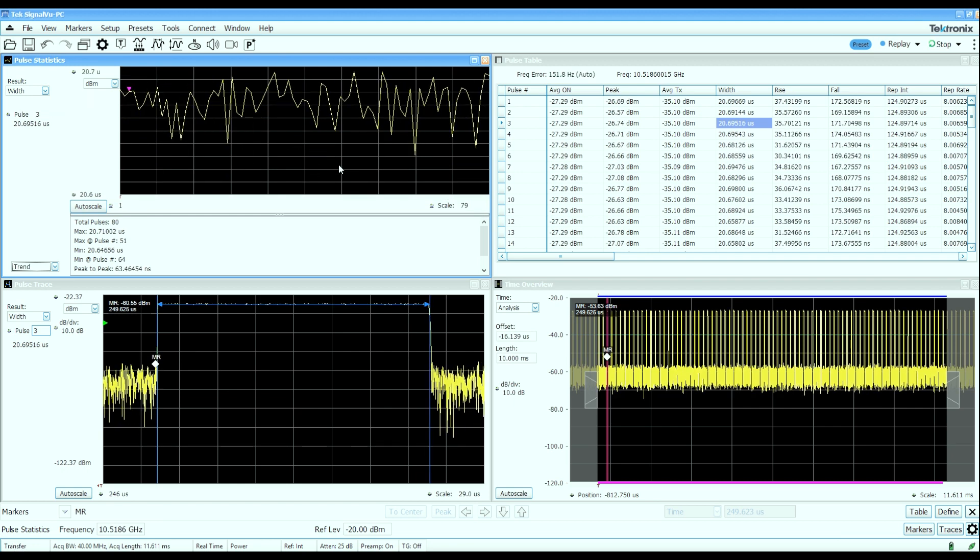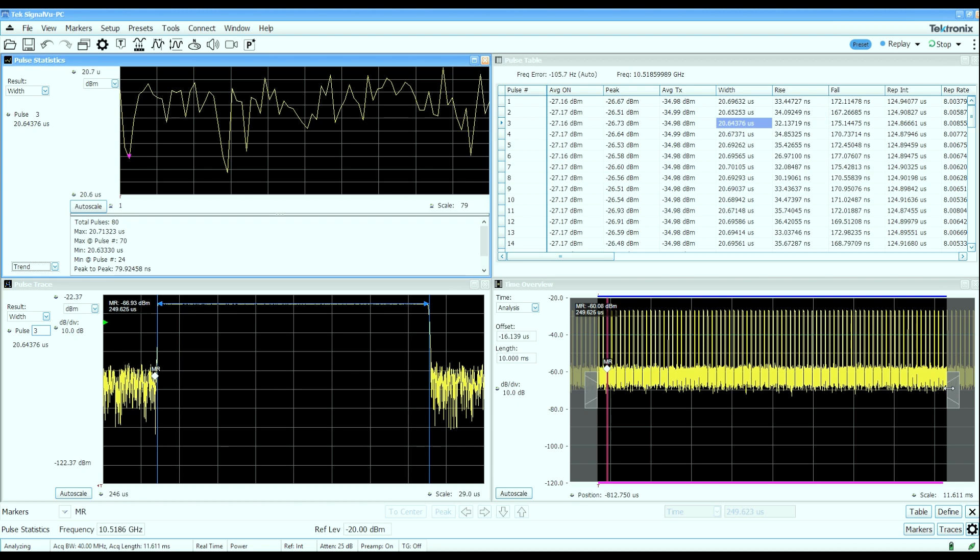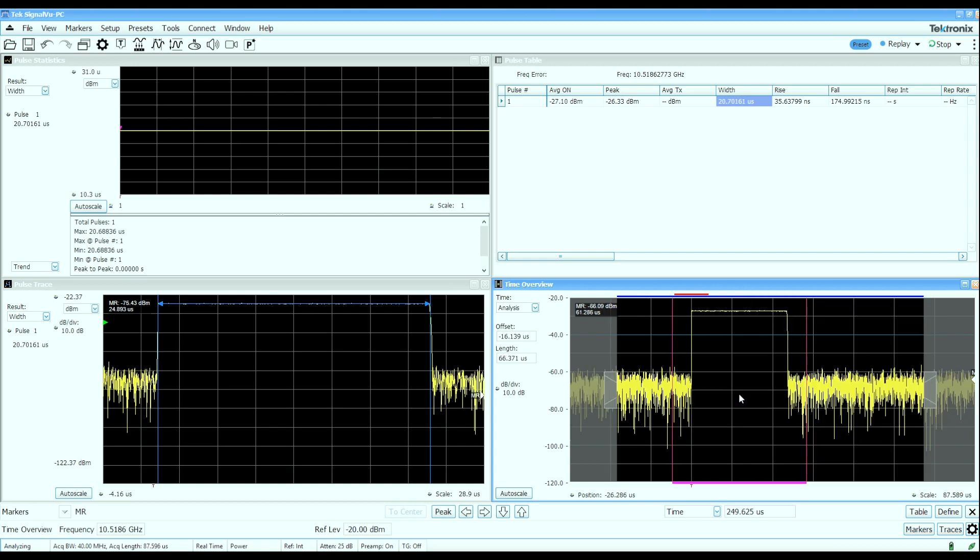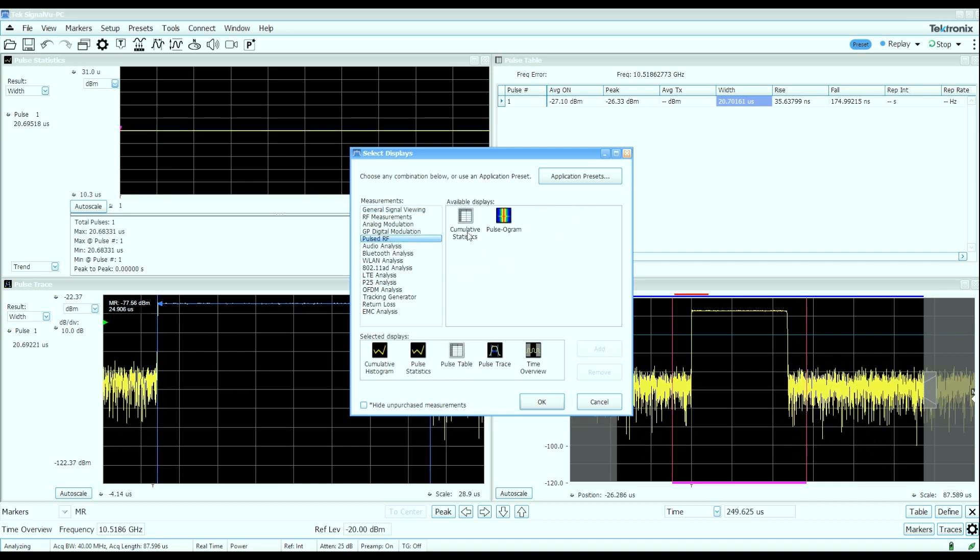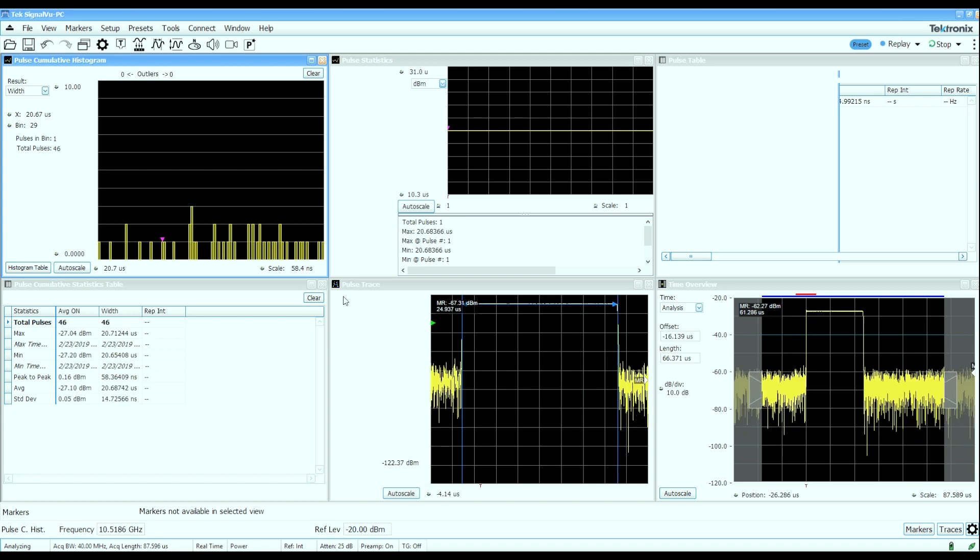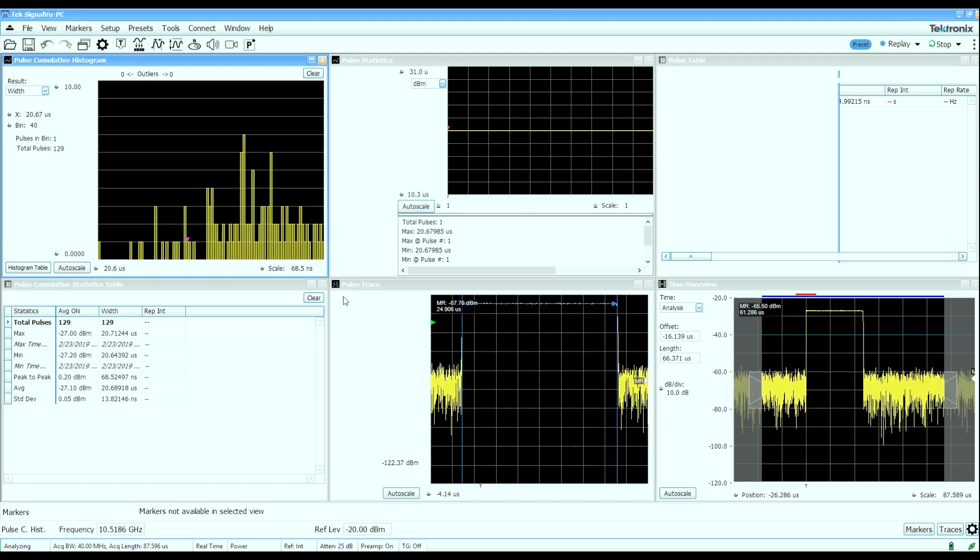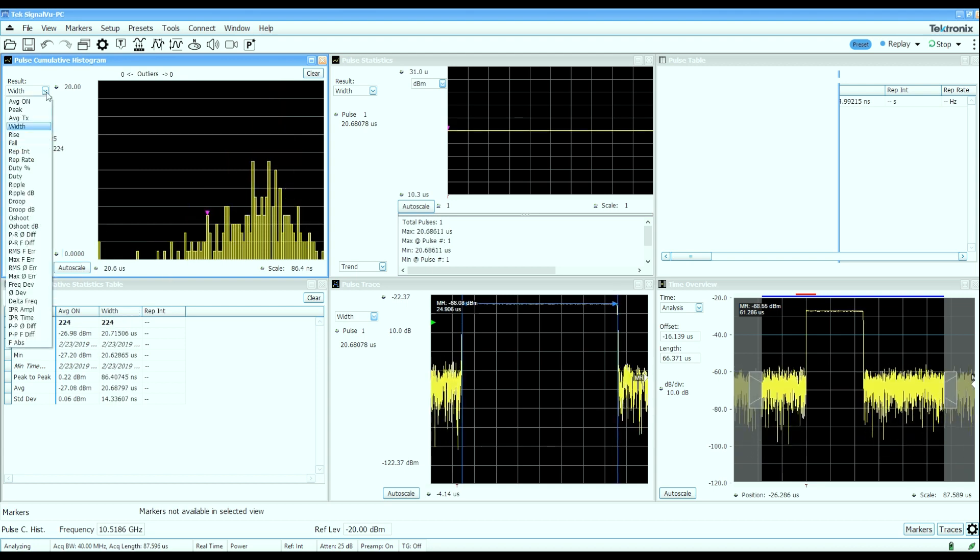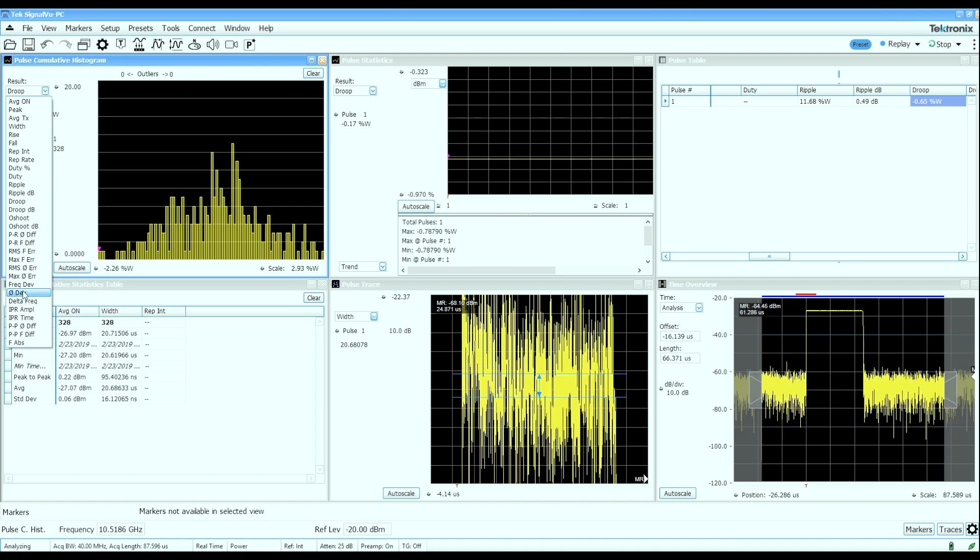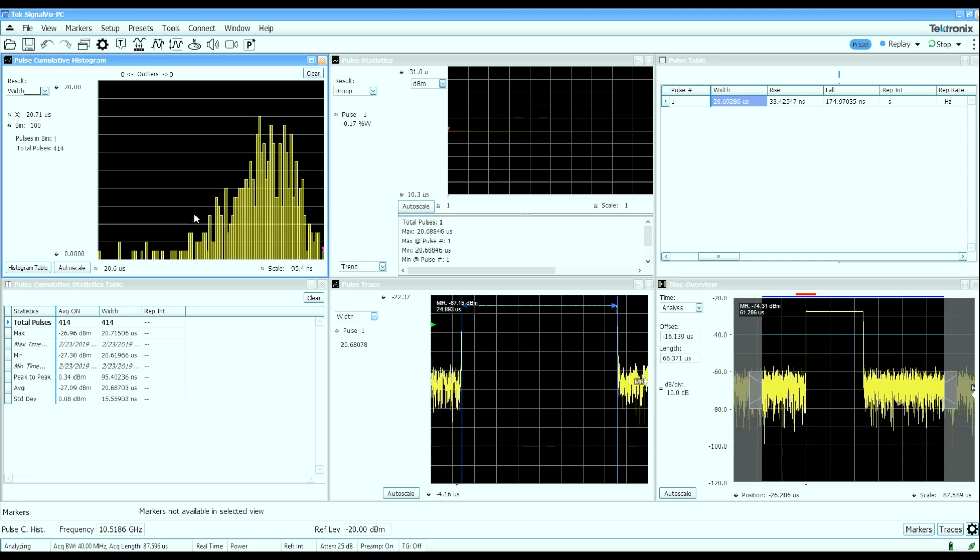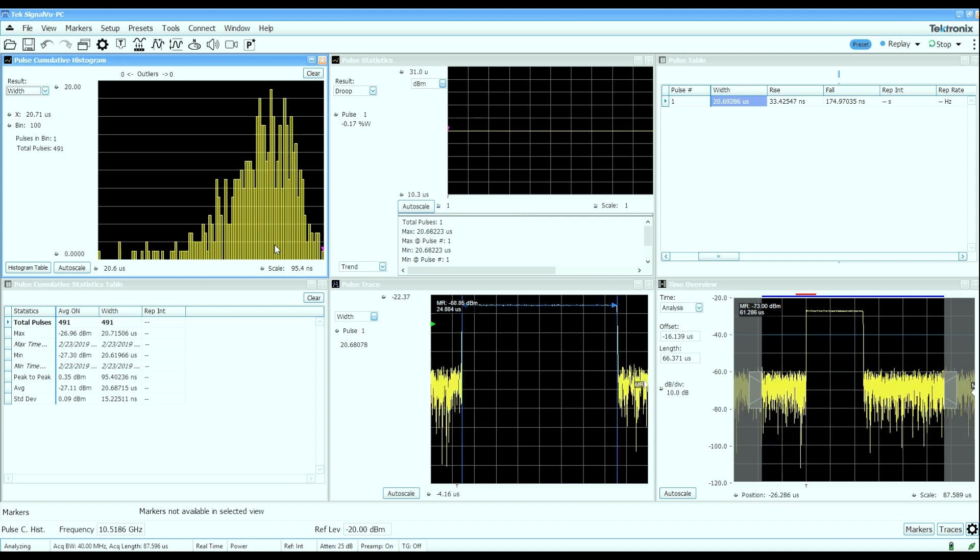Now, while the analyzer can capture a few seconds worth of data, you may need to have statistics over a much longer time period. You can adjust the time period in or out by simply adjusting the amount of analysis length that we have here. But you can also build cumulative statistics over a very long time period. And what we can do is bring up a couple of additional displays like a cumulative histogram and a cumulative statistics display. And these will just continue to build the results over time. So you can let this run and literally gather characteristics over hundreds of thousands or even millions of pulses. This will give you those cumulative statistics in a histogram form as well as in a table. And again, you can pick whichever measured parameter you want. All the statistics are being characterized for every single one of these parameters, so it's just a matter of picking and choosing what you want to have.